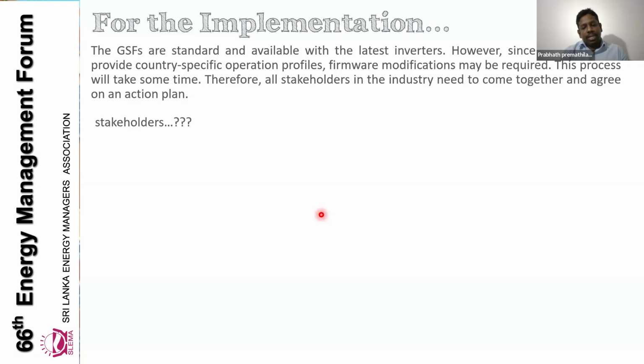But once we introduce this kind of feature to our Sri Lankan network, manufacturers will normally provide country-specific operation profiles. Since we are not requesting LVRT, or 10-minute sustained operation voltage tripping, or frequency droop characteristics for the moment, they may not be available in the Sri Lankan grid code. What I mean is that the inverter operation profiles for the Sri Lankan market may not be available. But firmware modification can easily be done, because each and every inverter is made for the international market, for international standards, IEEE standards, Australian standards, with the capabilities of these grid support functions.